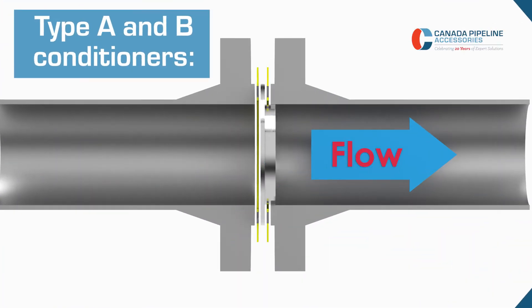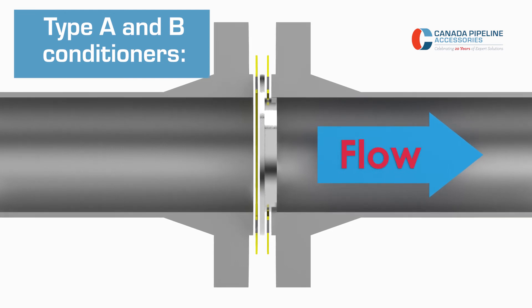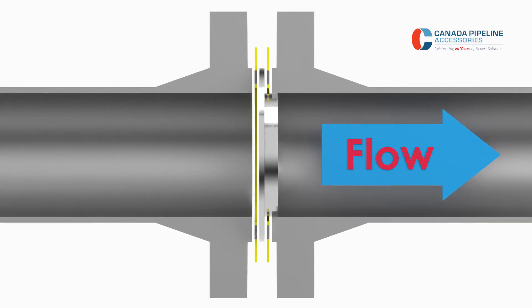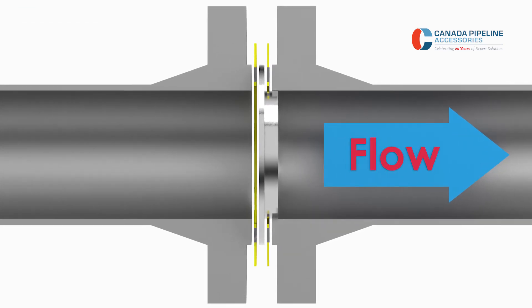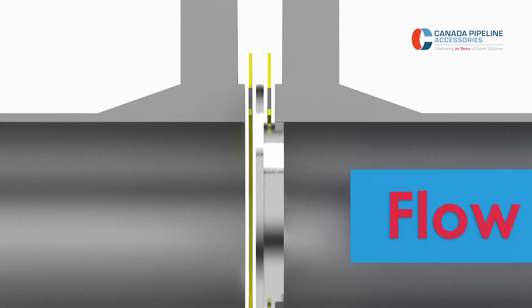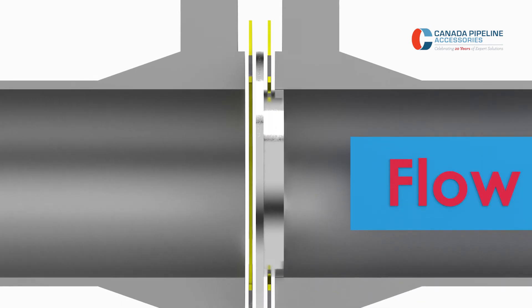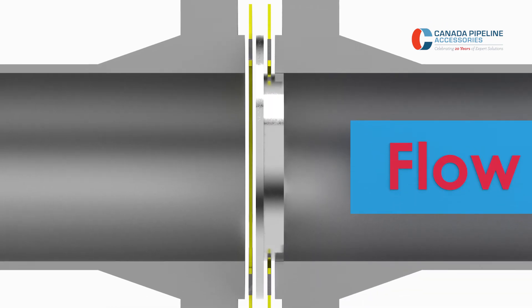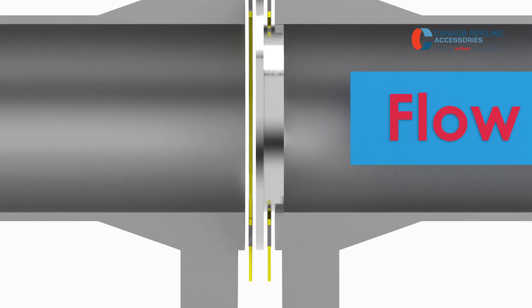For type A and B flow conditioners, the CPA will be sandwiched between two gaskets in the flange. CPA recommends spiral wound gaskets with inner and outer rings. The outer ring helps center the gasket in the flange itself to reduce the chances of the gasket sliding in front of the flow conditioner, which can cause a measurement error.